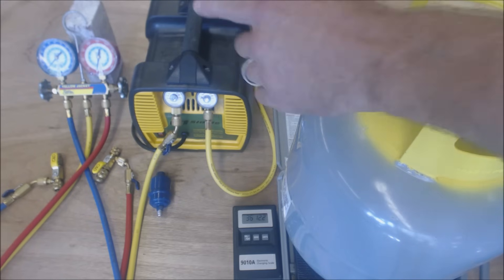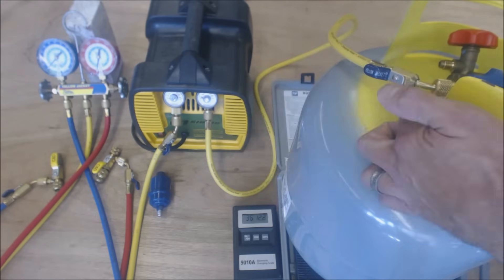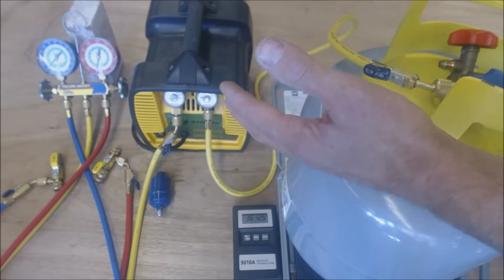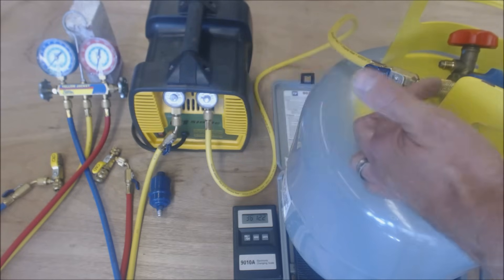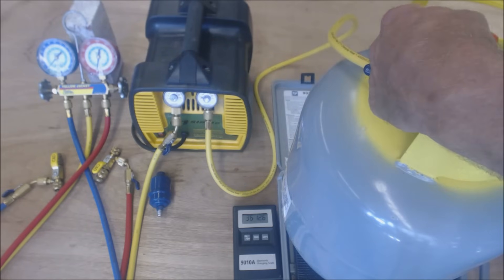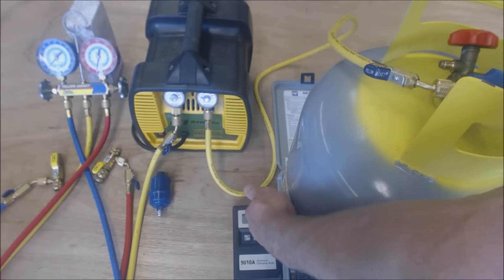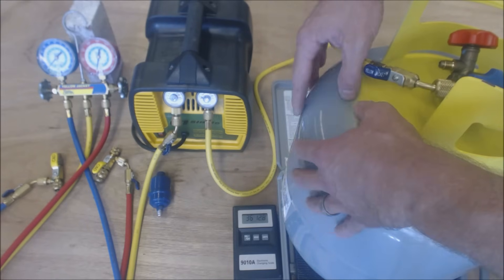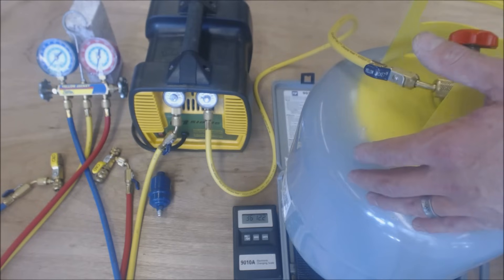If we're going to recover in vapor form, we can put it into the vapor port. If we're going to recover in liquid, we can put it into the liquid port. I will tell you that regardless of whether you're recovering in liquid or vapor, if you put it into the vapor port, usually you're okay. If you try to recover in vapor, make sure that you're not putting it in the liquid port because the liquid port has a dip tube that goes all the way down to the bottom. Basically you're putting vapor down there and it's bubbling up through the liquid, and it causes the tank to get really hot.